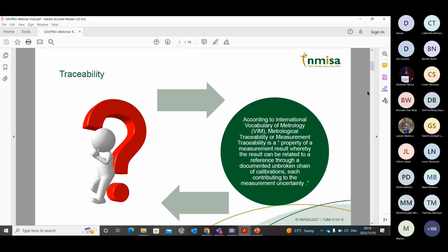So if we look at the definition of traceability, you can see that there are three things that we have to look at. One being the calibration, second, the reference, and third, the measurement uncertainty. So when we're talking of traceability, we are actually looking at a measurement that is a quantity that links the measurement to the international community.